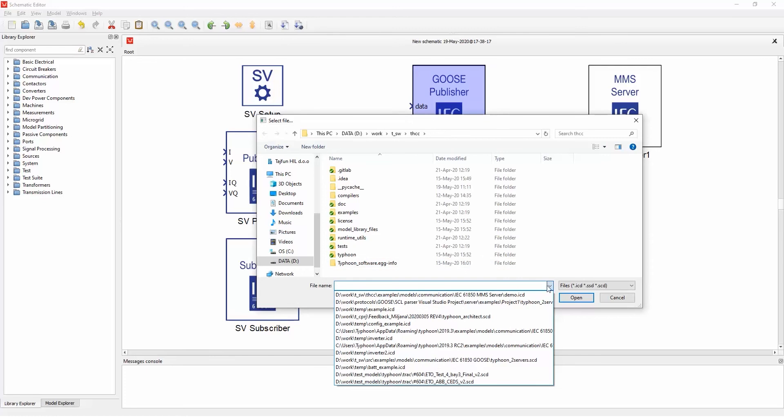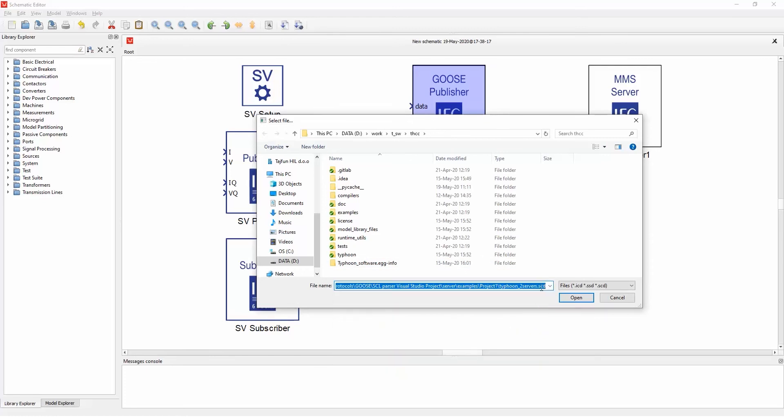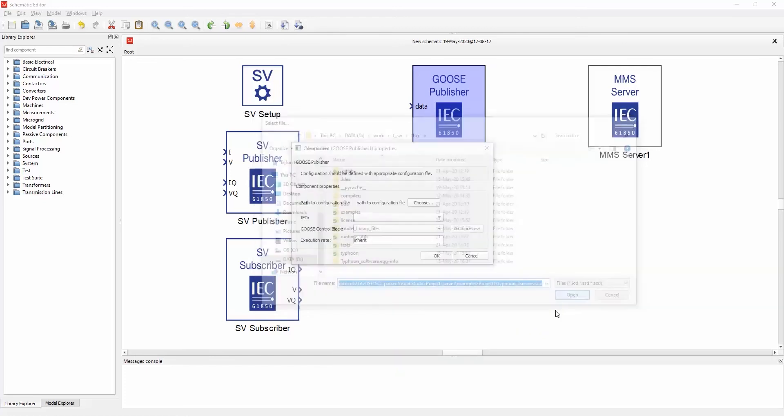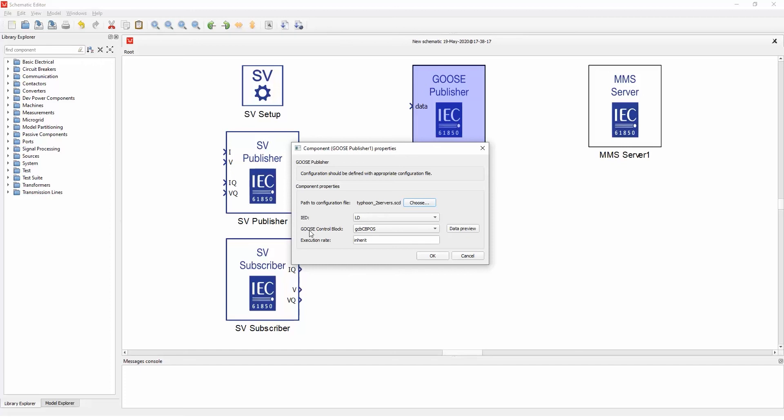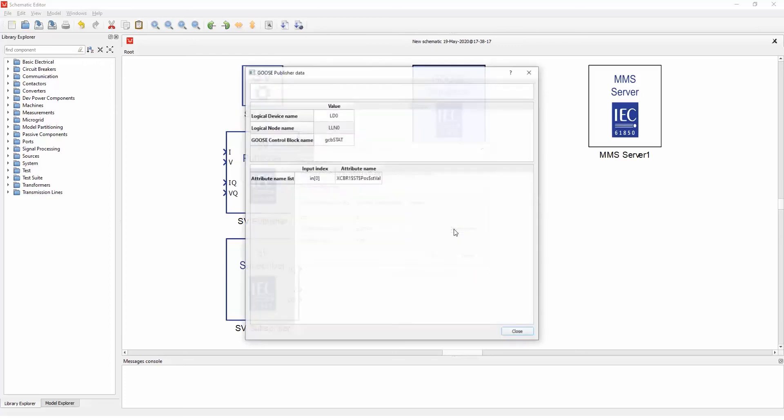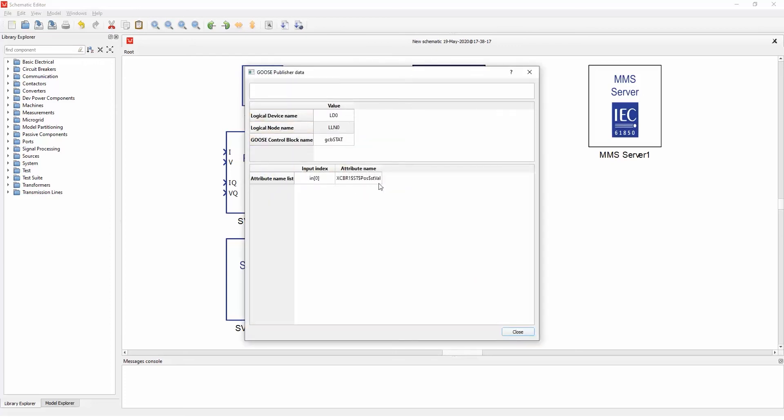So if I select some SCD file here, these combo boxes fill with data from that file, and you can select the ID if multiple IDs are specified in this configuration, and you can select the Goose control block that you want to emulate. So here we have three of them specified. You can select one and you can also see the data that is present for that Goose configuration block. As you can see, the logical device name, logical node name, etc., and the data that is sent.